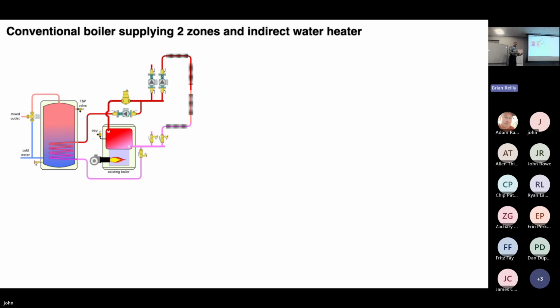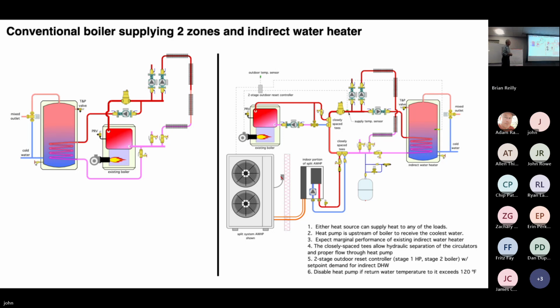And by the way, when I show you the makeover, that's just one option. There's probably half a dozen acceptable alternative piping layouts that you could use. I just want to show you examples that are using the concepts we talked about earlier. Okay, so here's one. This requires a little bit more rearrangement. I'm trying to minimize the disruption of the piping out here. So remember, one of the concepts I showed you earlier was instead of putting the 2 heat sources, the heat pump and the boiler, in parallel, we could connect each using a set of closely spaced T's to a common loop that then goes out and serves all those loads.